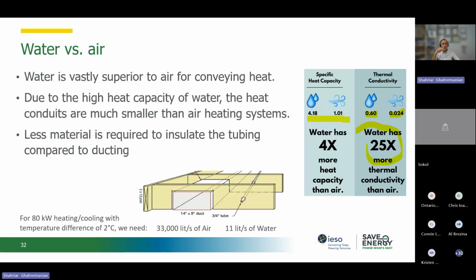I have one example here. For 80 kilowatts of heating and cooling with a temperature difference of just 2 degrees Celsius, we need to provide 33,000 liters of air per second. But for the same amount of heating and cooling within that temperature difference, we need to provide just 11 liters of water. So you see the difference between the fan operation and volume we need to move versus the pump and pipe size. That's the beauty of hydronic systems.